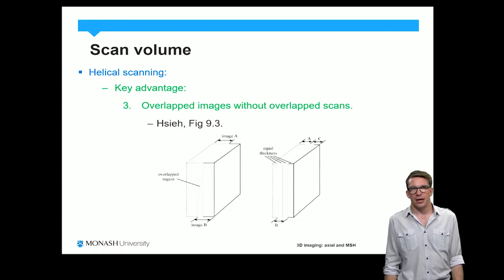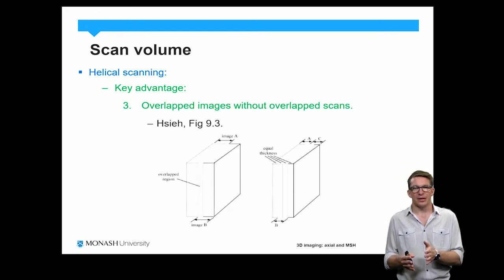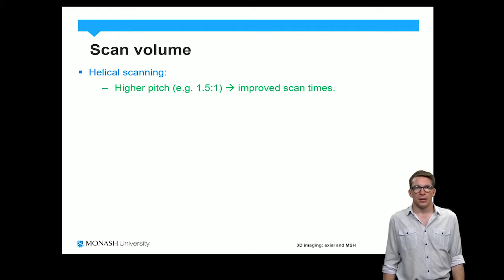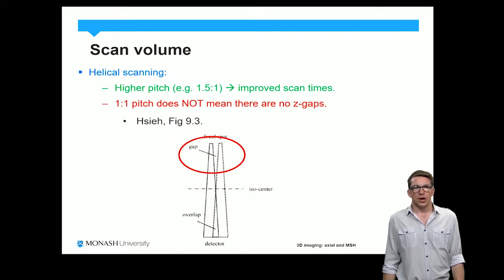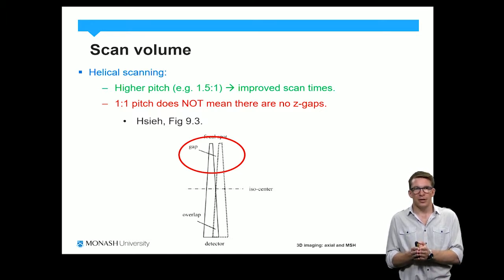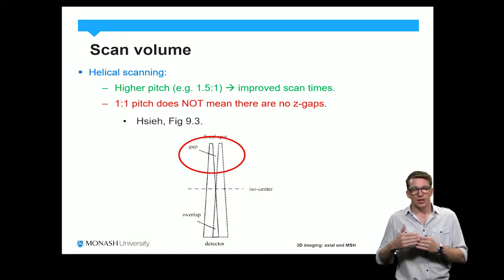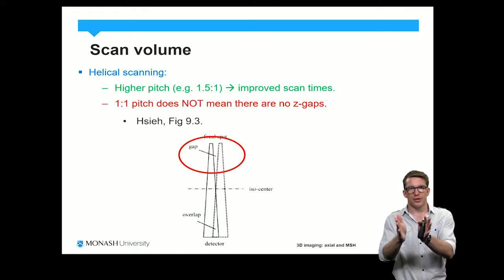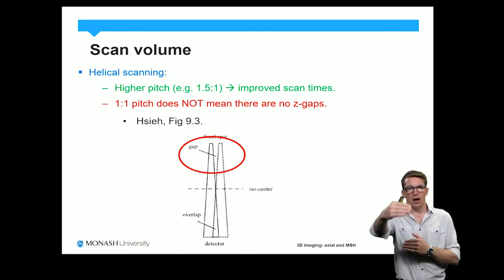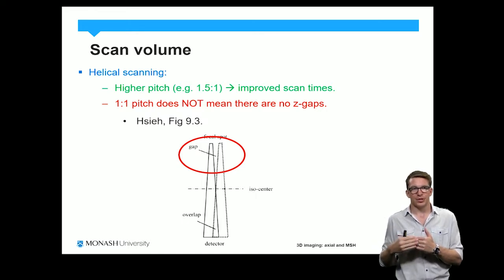Another advantage is that we can reproduce overlapping images without actually overlapping the scan, just by going back and selecting the data in the way that we require. One thing to note is that even if we have a pitch of one, it does not mean that there are no gaps in Z. Because of the divergent nature of the beam, as we move from the source towards the detector we have this degree of divergence, which means we therefore have overlap towards the detector surface and gaps towards the source.